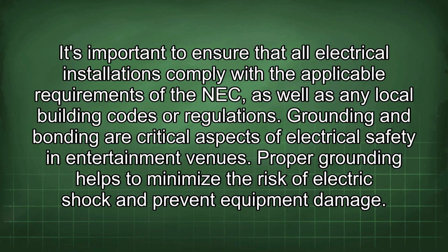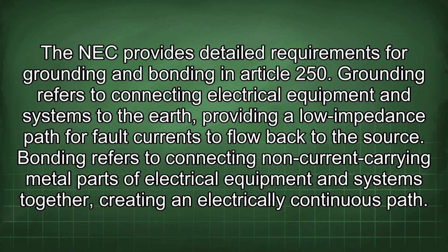Grounding and bonding are critical aspects of electrical safety in entertainment venues. Proper grounding helps to minimize the risk of electric shock and prevent equipment damage. The NEC provides detailed requirements for grounding and bonding in Article 250. Grounding refers to connecting electrical equipment and systems to the earth, providing a low impedance path for fault currents to flow back to the source. Bonding refers to connecting non-current carrying metal parts of electrical equipment and systems together, creating an electrically continuous path.